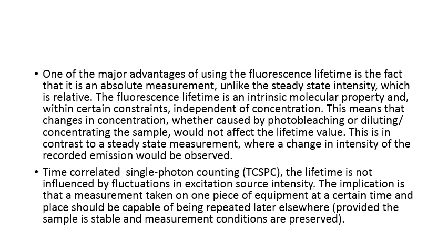whereas your intensity may depend on concentration. This means that changes in concentration, whether caused by photobleaching or diluting the sample, would not affect the lifetime. This is in contrast to steady state measurement, where a change in intensity would be observed. That is why lifetime measurement is very essential and beneficial compared to other measurements that we do.